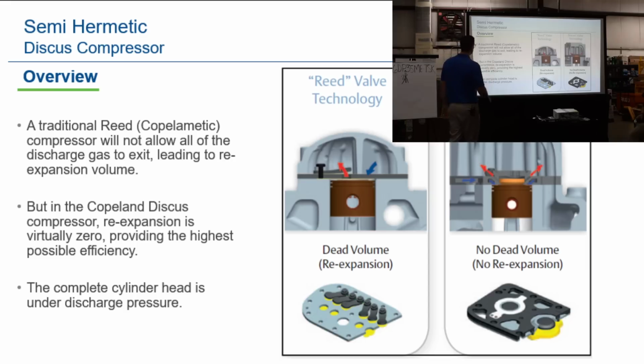Okay, Discus compressor. So this technology is not new. We developed the Discus technology in the 80s. So the traditional Reed Copeland compressor will not allow all the discharge gas to exit. Like I showed you where that volumetric efficiency loss is, right? So that's re-expansion of gas. So as that piston pulls down again, it has to force that discharge open a little bit to pull the gas out, right? So you're fighting.